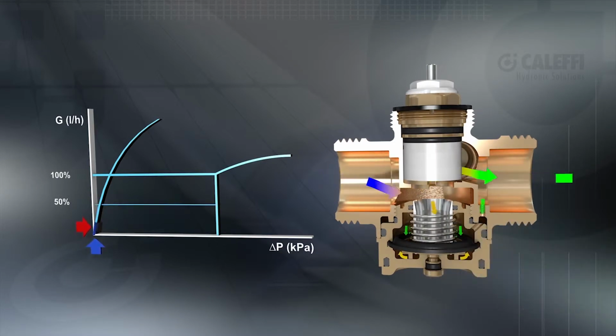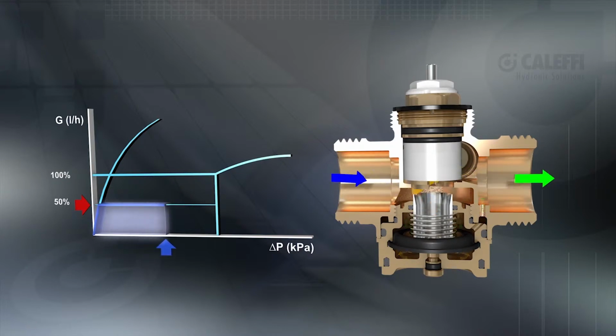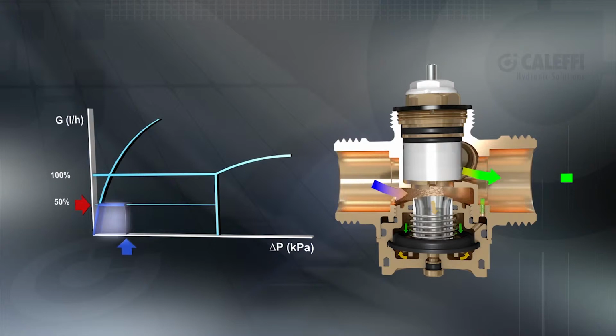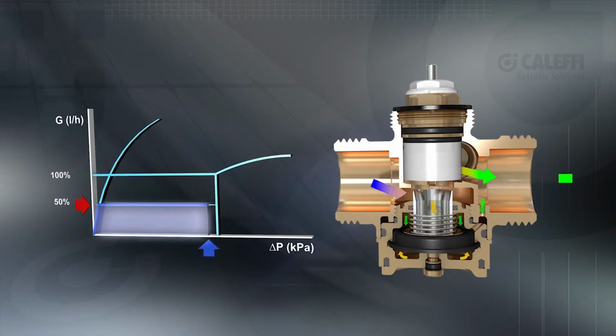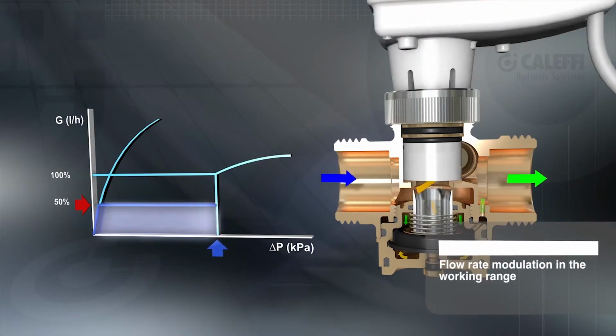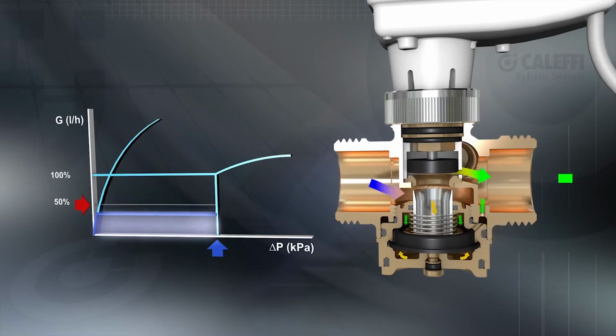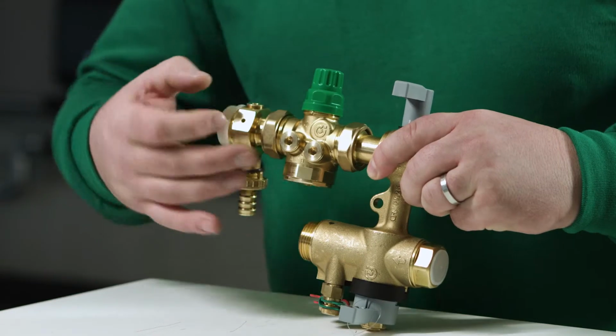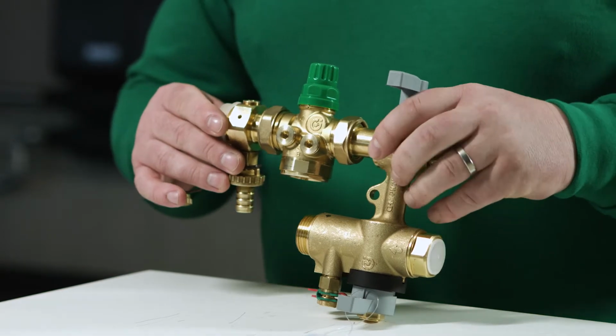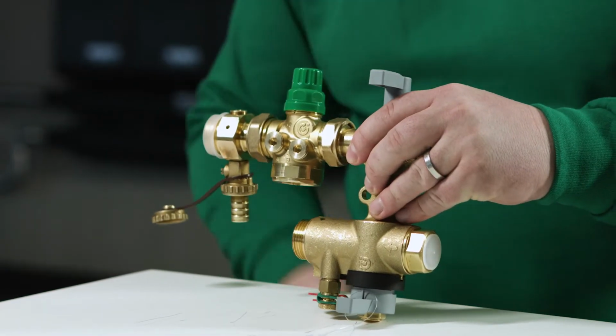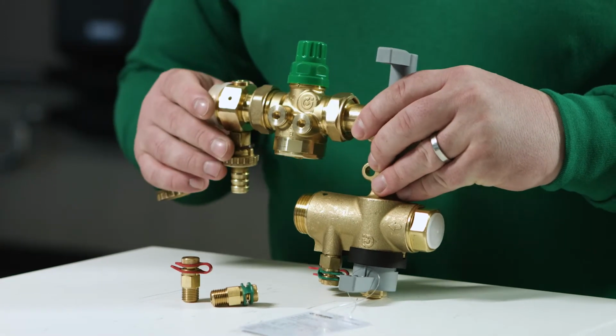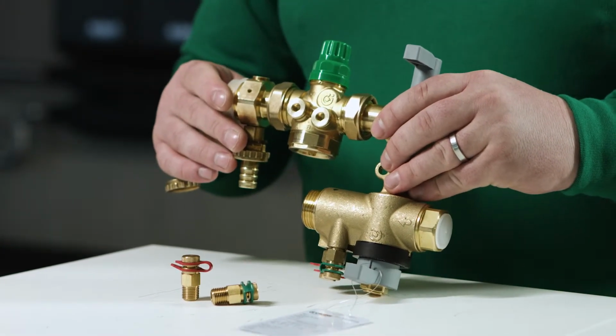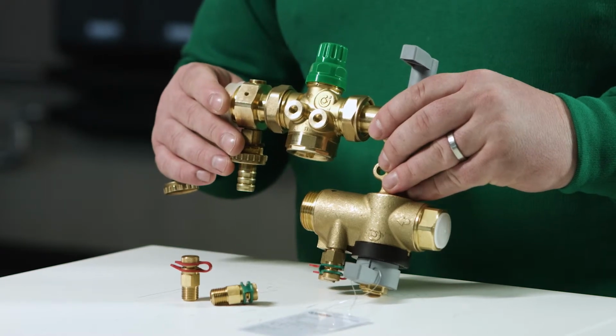The valve will modulate to control the delta P. The valve controls delta P to ensure the flow rate remains constant at the preset value, regardless of changing system conditions. Also, using the actuator, the valve can adjust the flow rate depending on the system demands. Using the 2 pressure ports on the PICV body, there is a possibility to connect a measuring device. This passage is important to make sure we have the correct differential pressure to guarantee the PICV functioning.